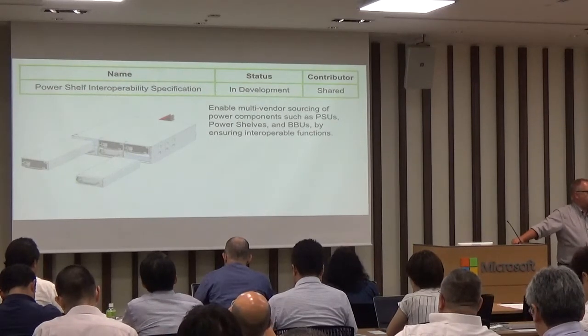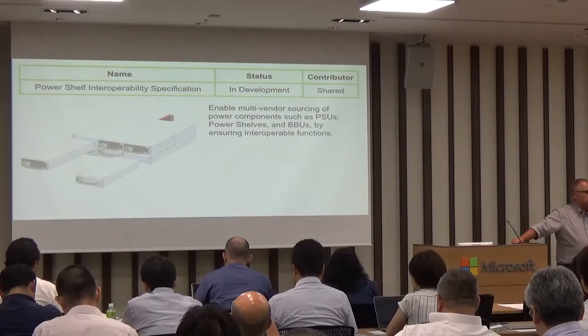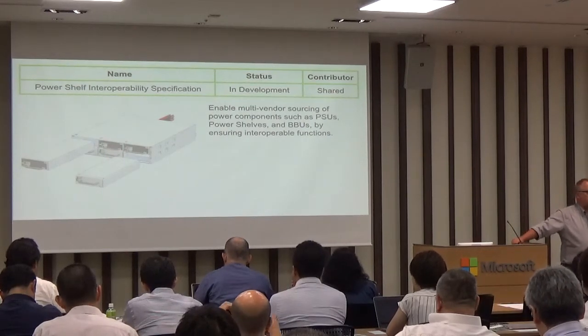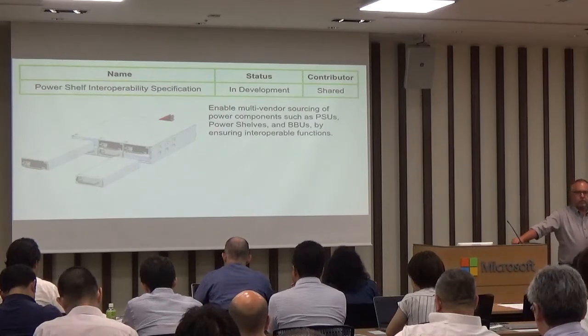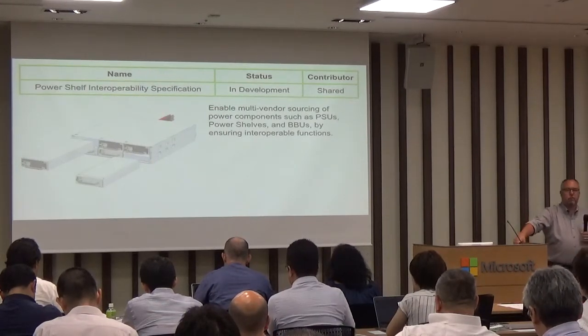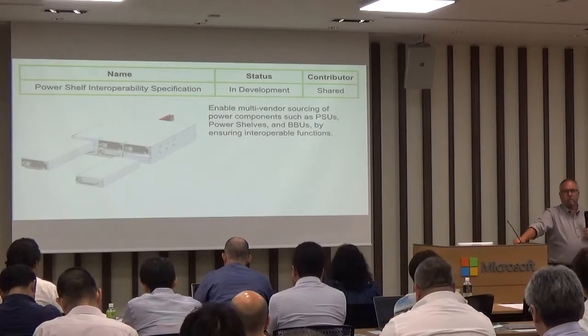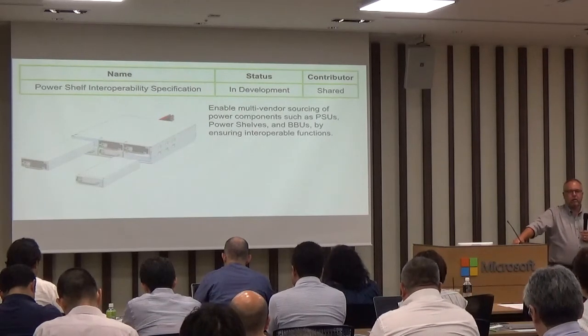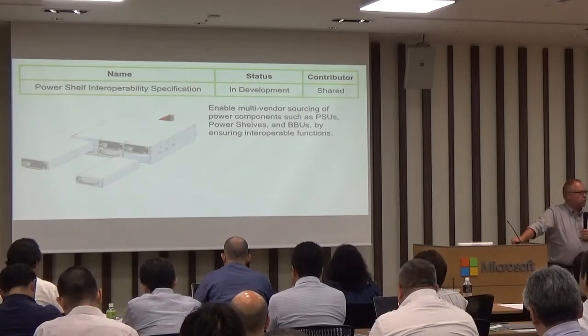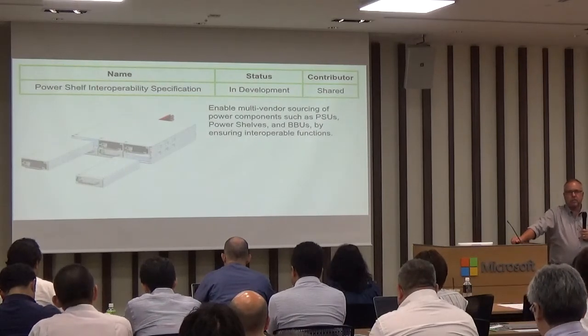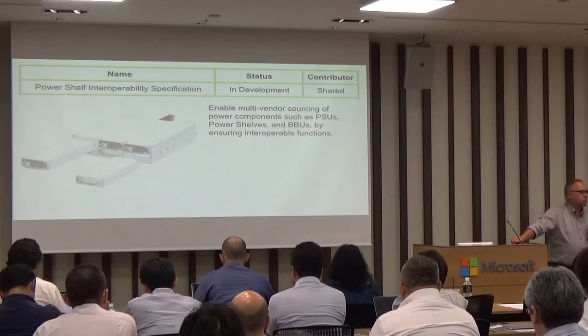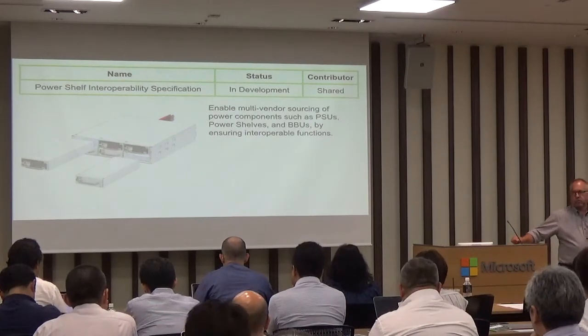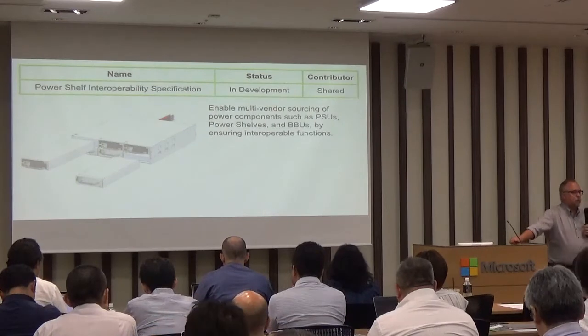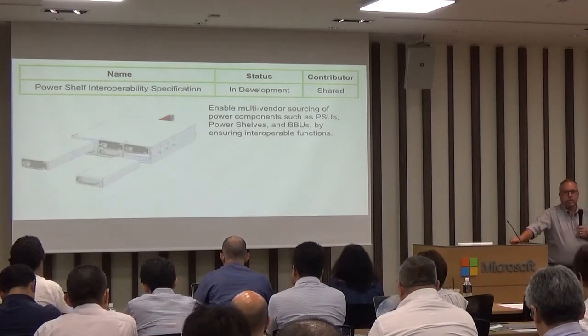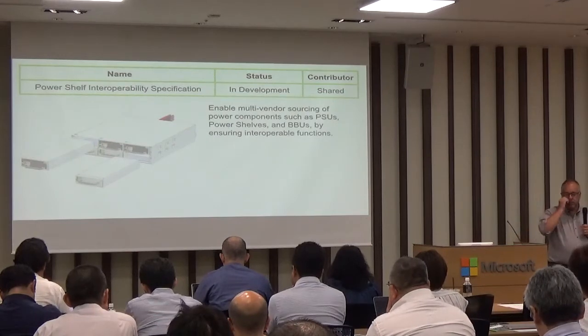We may have a 4 kilowatt rack where you can use very low cost, low output rectifiers. In the same rack, or another data center, you may want to support 25, 30, or 50 kilowatts of power, so you'd want a much higher rated module plugged into the front. In this picture, you can see 6 power modules that give options for 3+3 resiliency, 5+1 resiliency, or you can put them all together for one massive 6-unit system.